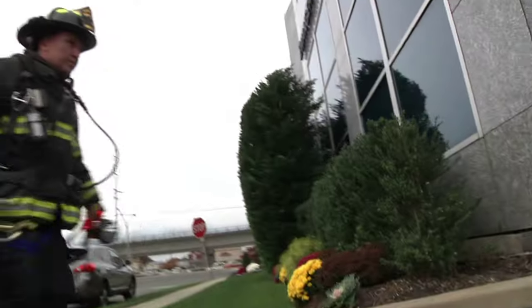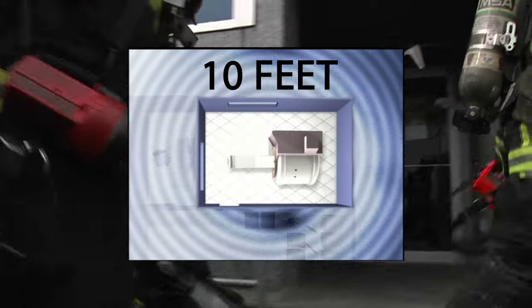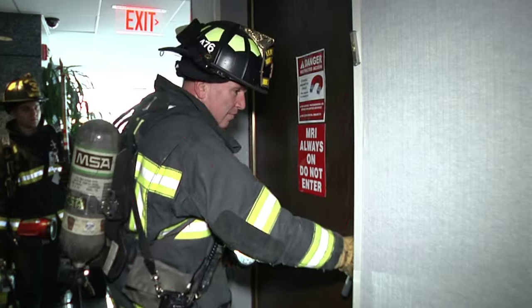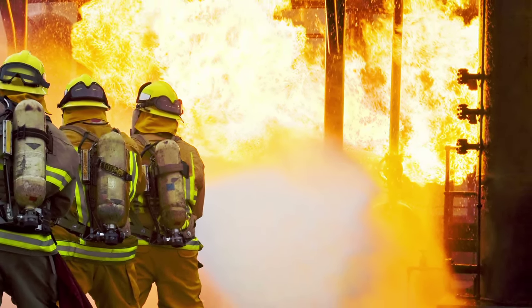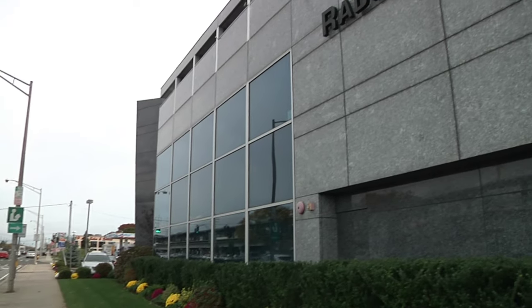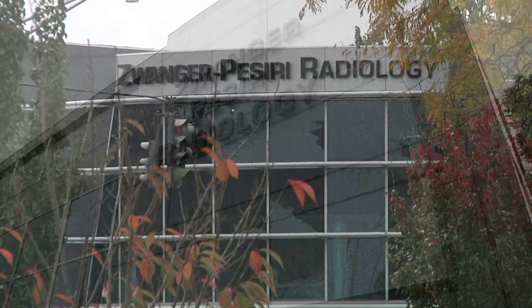When responding to a fire at an MRI facility, normal firefighting techniques can be used while maintaining a distance of at least 10 feet from any MRI unit. Be sure to recognize any MRI rooms and do not enter unless you are completely metal free. If there is a fire in the actual MRI room, it should be extinguished only with a non-ferromagnetic extinguisher or attacked from outside the MRI room. Be sure to locate the stop and quench buttons near the MRI technologist console area. Remember, the emergency stop button turns off electrical power to the MRI only and does not turn off the magnetic field. Upon arrival at the facility, be sure to locate the office manager, who will help guide you through the facility and alert you of any dangers to be aware of.